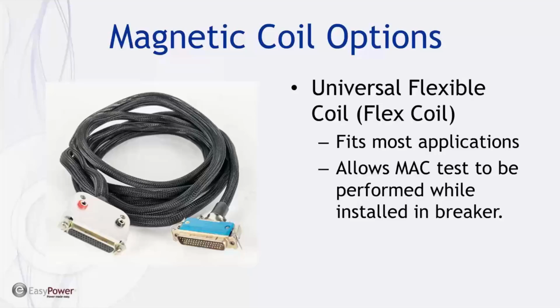still installed. So basically, this coil is just a bundle of 50 wires, and on the connector, each pin is offset by 1. So when you connect it together, it makes a continuous circuit from input to output, and so each wrap is actually 50 wraps. So with those 5 wraps, you're in essence getting 250 wraps of this wire around the vacuum interrupter.